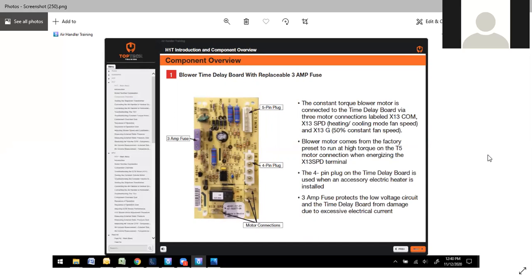The constant torque blower is connected via the time delay board via the three connections. X13 common, that's your common. X13 speed, SPD, which is going to be your heating, cooling, fan speed. And then you have an X13G, which is basically 50% of your constant fan speed. So not quite an ECM, but you get some of the same benefits. Blower motor comes from the factory preset to run on high torque, which is T5 motor connection when energizing the X13 speed.